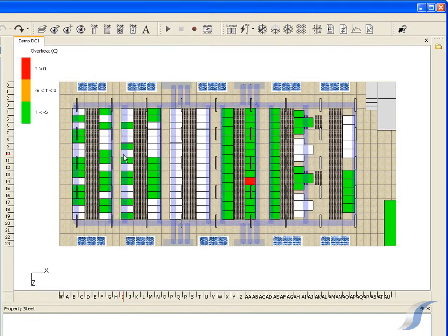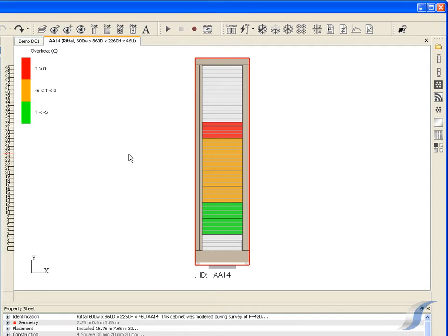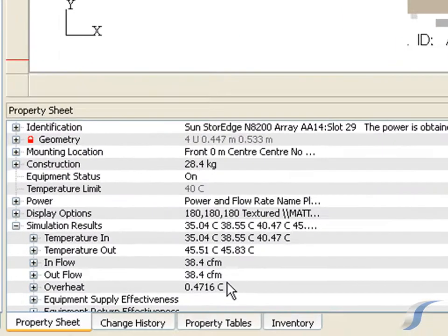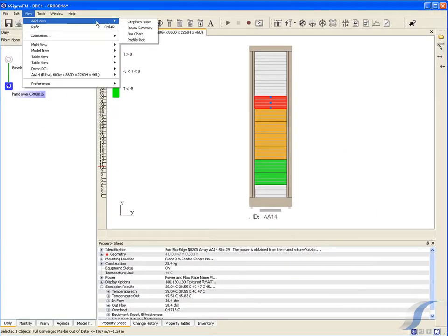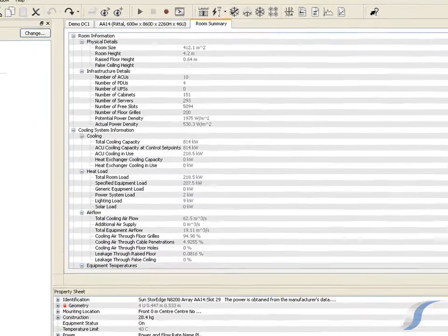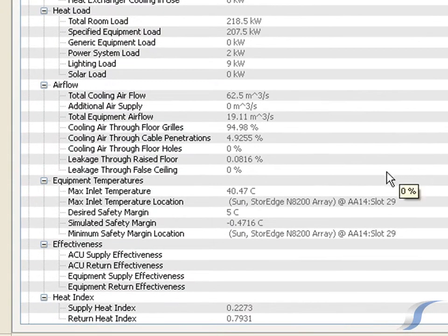Looking at the equipment overheat plot, we see that all cabinets achieve the required safety margin of 5 degrees C for this data hall, except cabinet AA14. Looking more closely at that cabinet, we can see that one piece of IT equipment is predicted to overheat, and four more do not achieve the required safety margin. We can create a Room Summary using View > Add View > Room Summary, which shows information about the room in tabular form. The Equipment Temperatures section confirms that the equipment in slot 29 of cabinet AA14 is predicted to overheat by 0.5 degrees C.